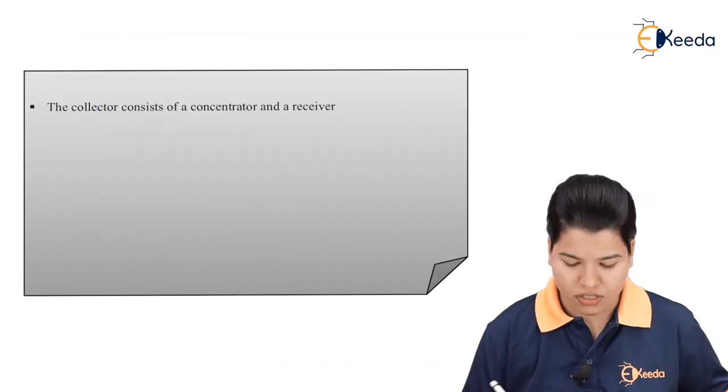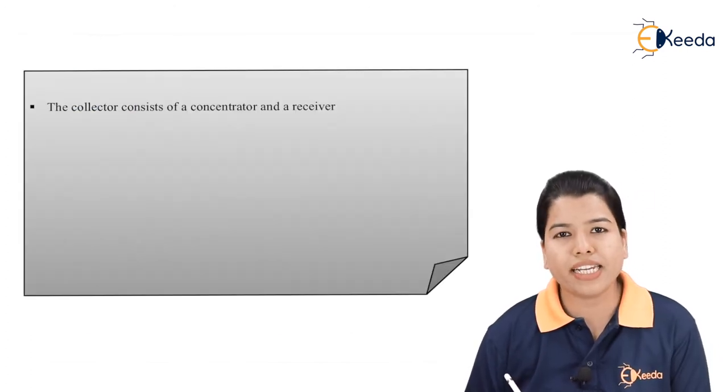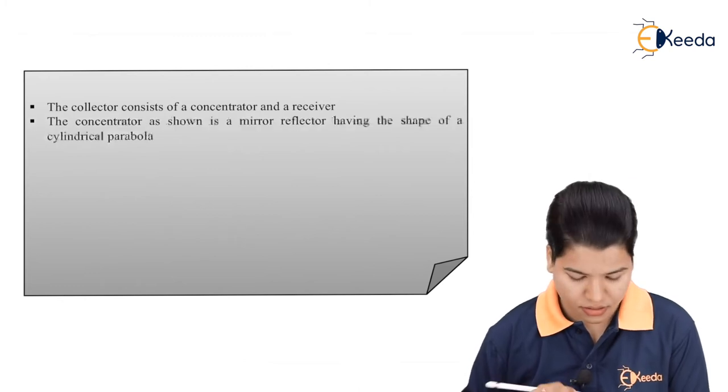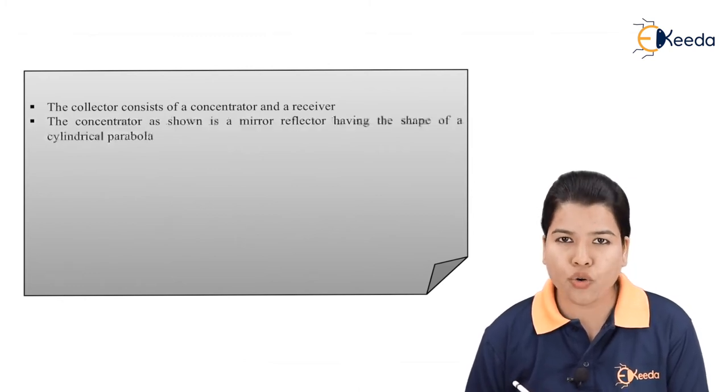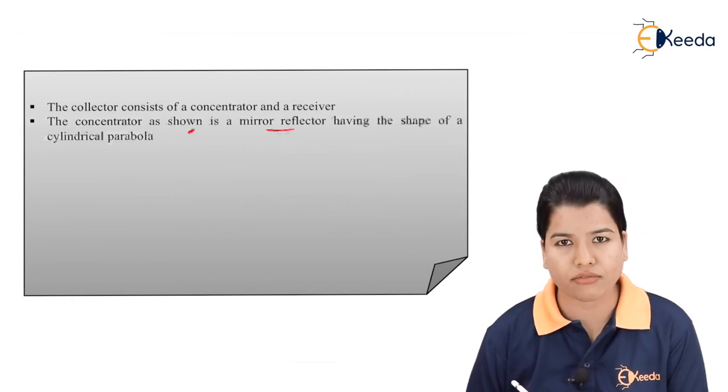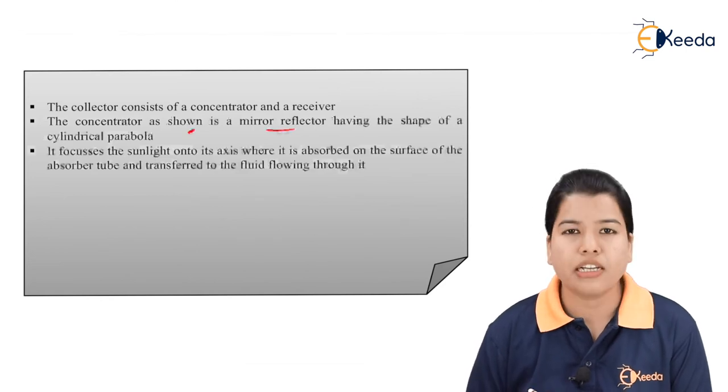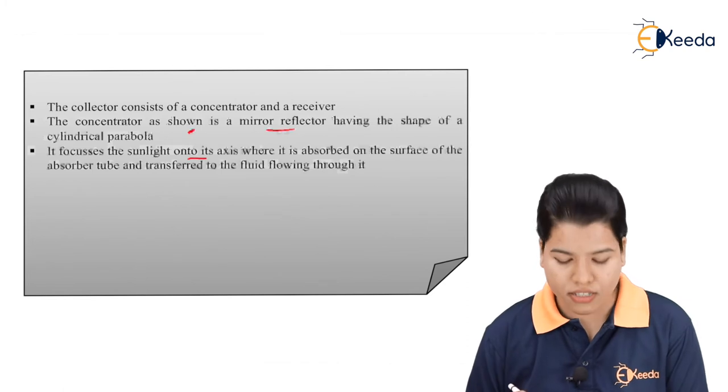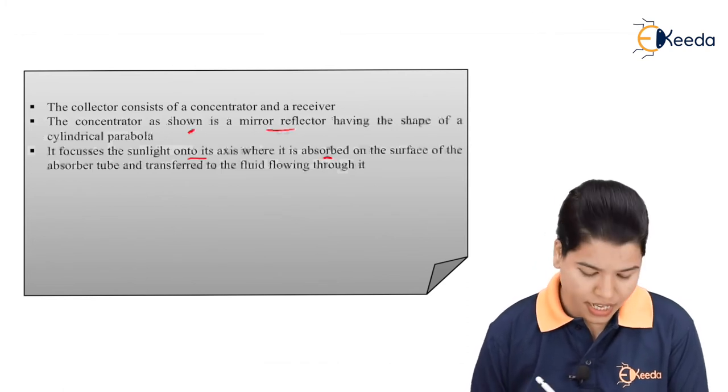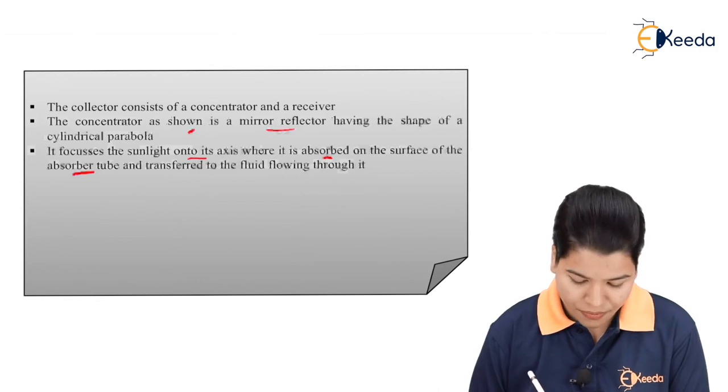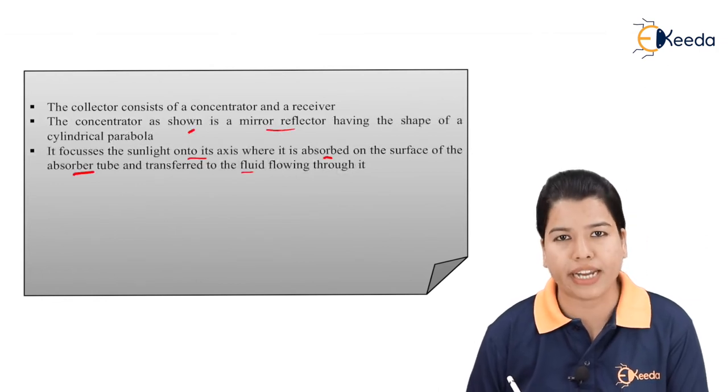Let us see its working. The collector basically consists of one concentrator and one receiver. The concentrator shown in figure is a mirror reflector having the shape of the cylindrical parabola. It basically focuses the sunlight onto its axis where it is absorbed on the surface of the absorber tube first and then it is transferred to the fluid flowing through it.